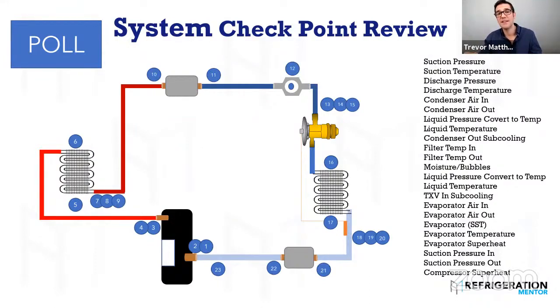So it knows exactly, and you'll see these on refrigeration condensing units with evaporators with distributors on it, because there's multiple circuits. So it wants to make sure it knows exactly the pressure for all those different circuits going in there to tell that TX valve what's going on. If that's plugged or installed wrong, or you cap it, you're going to run into major issues. And then something plugging it, like copper debris plugging the metering device. Great job on answering that question.